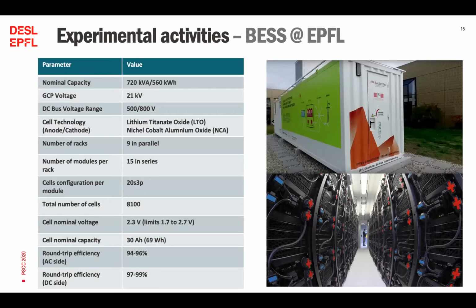Here are some numbers regarding our installation on campus. As I mentioned before, it has a rated power of 720 kVA and a storage capacity of 560 kilowatt hours. The technology is lithium-ion LTO, so with lithium titanate oxide cells. And the configuration has a total of 9 racks. In this particular case, we have used only 7.